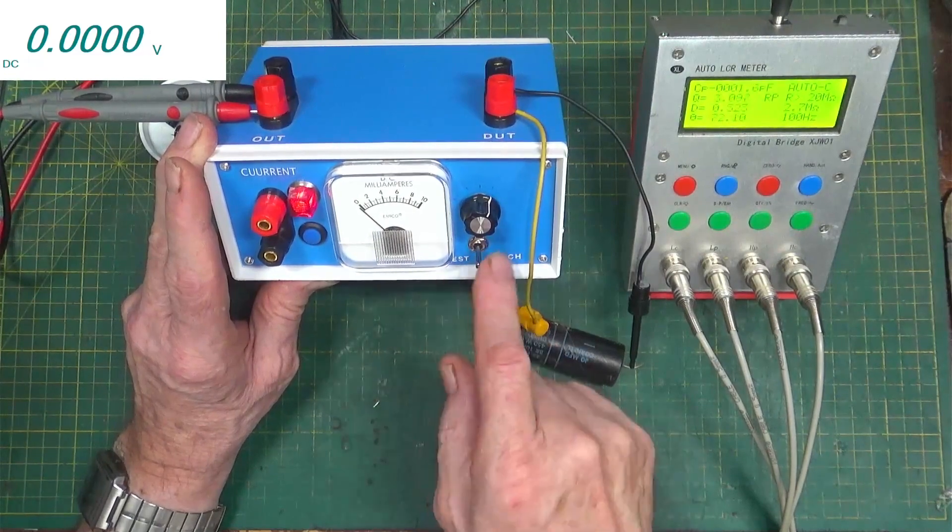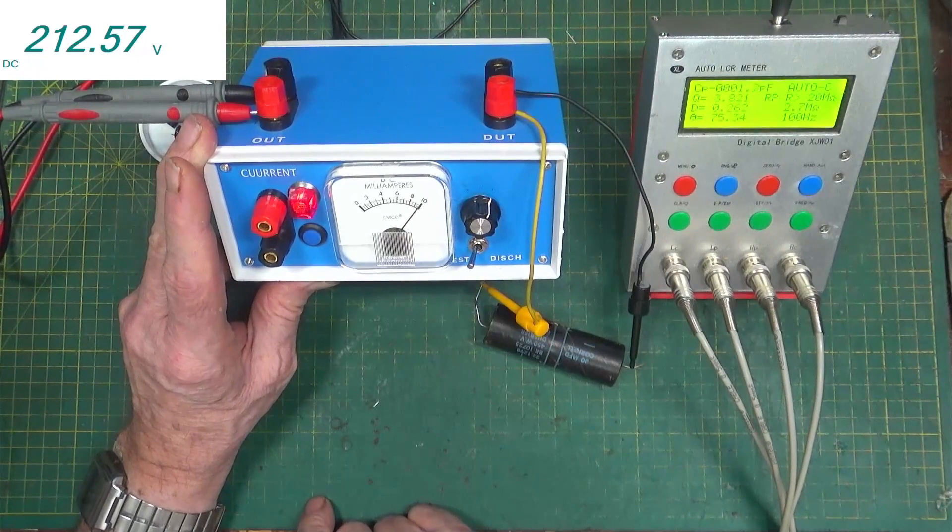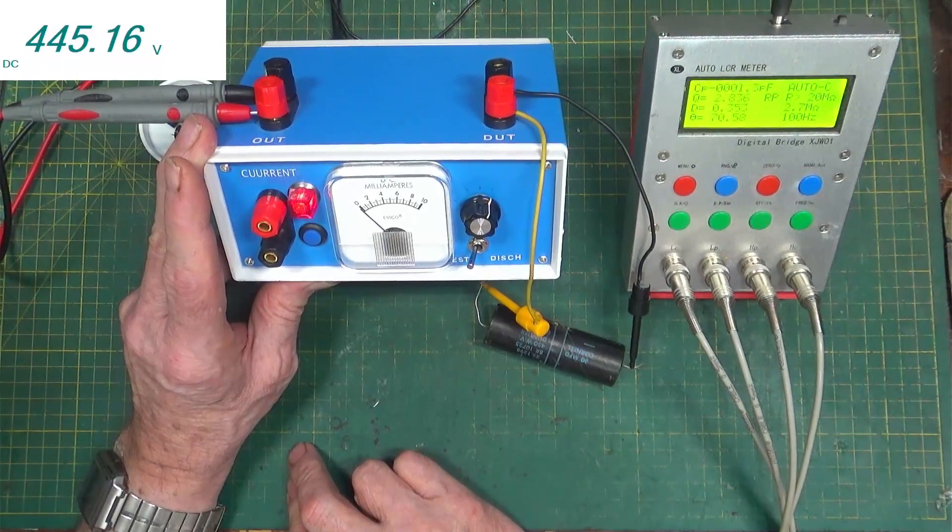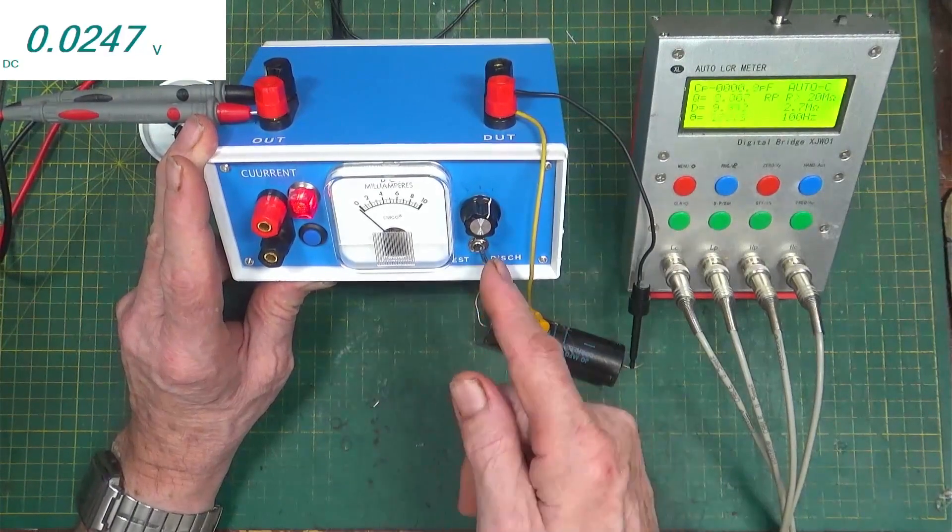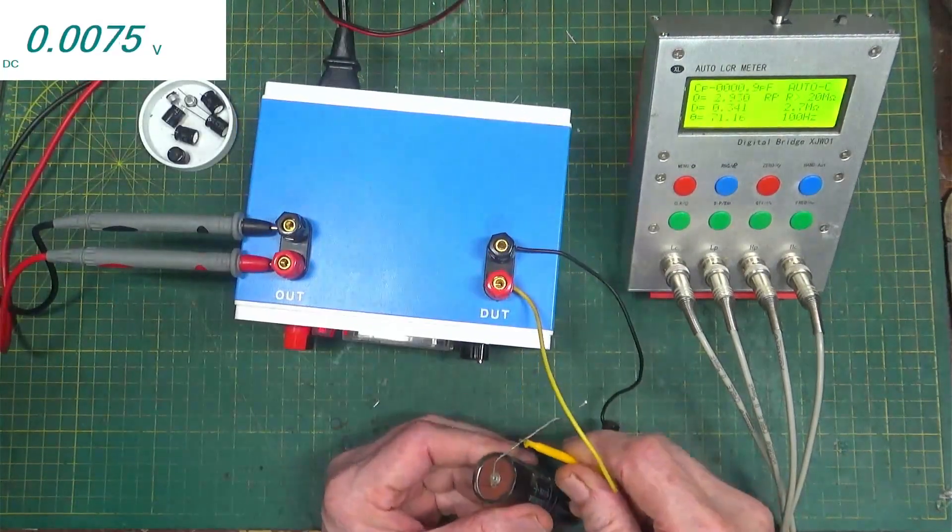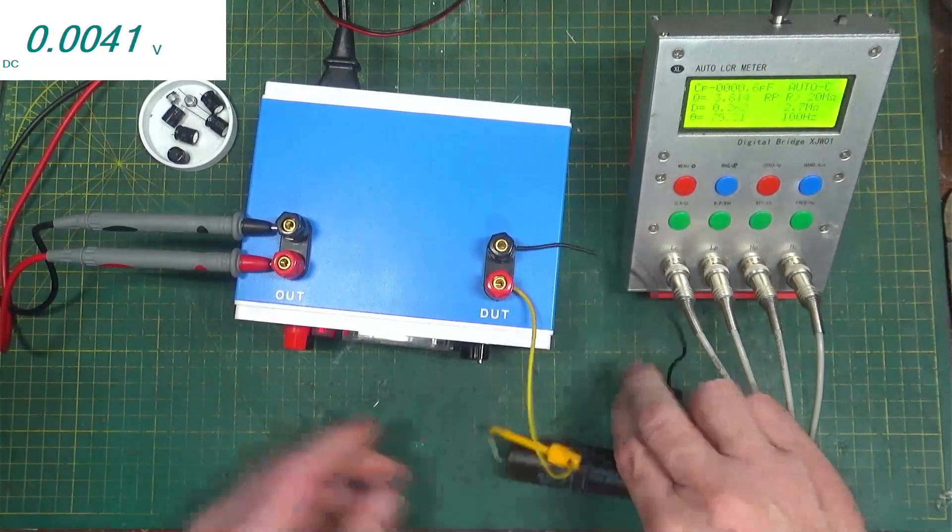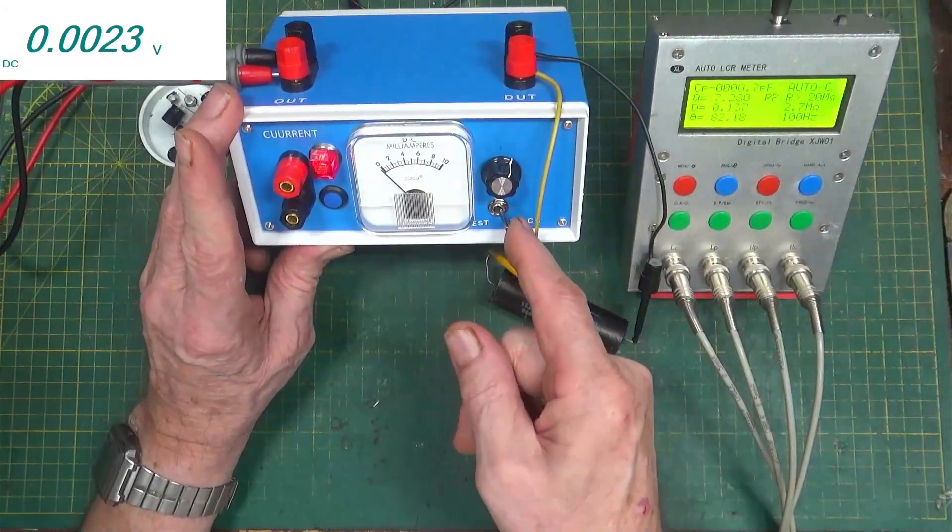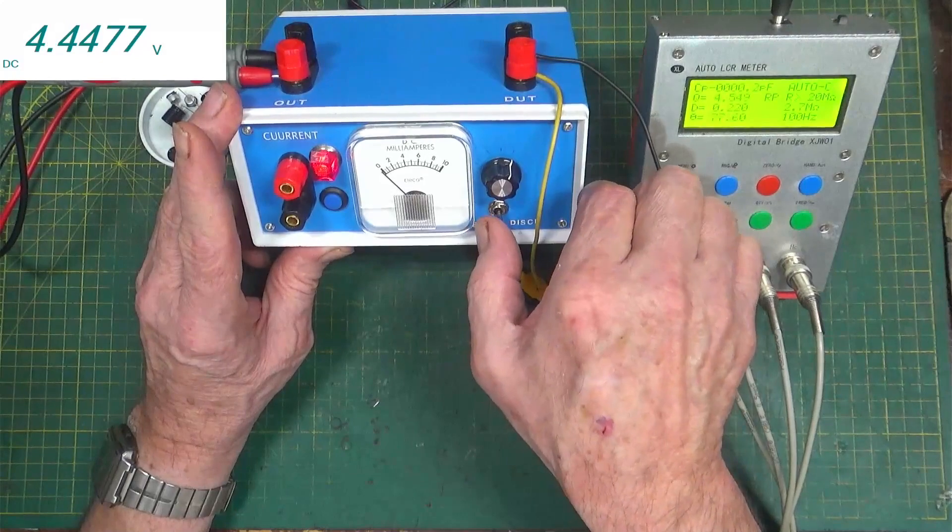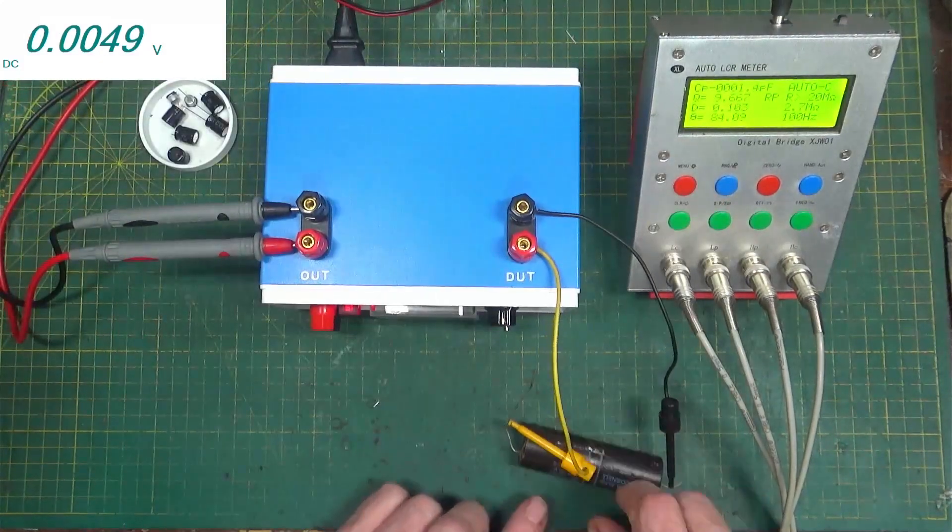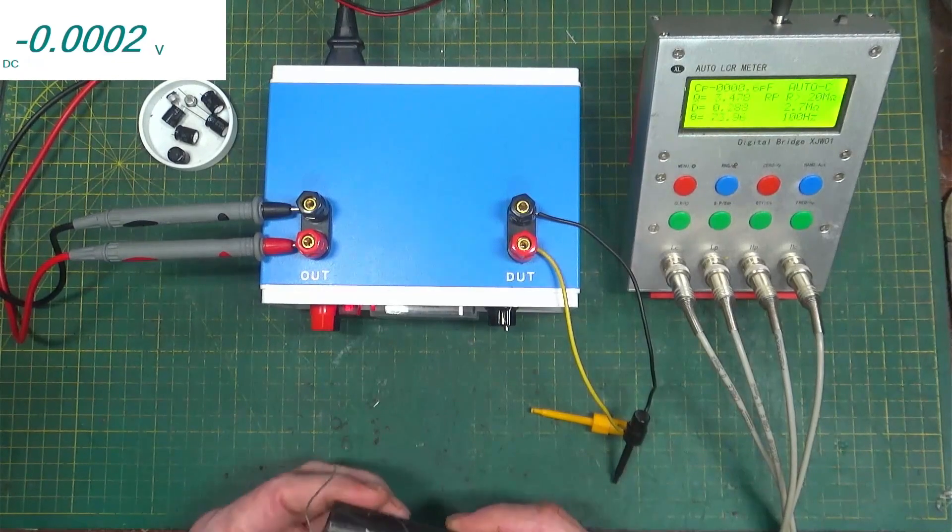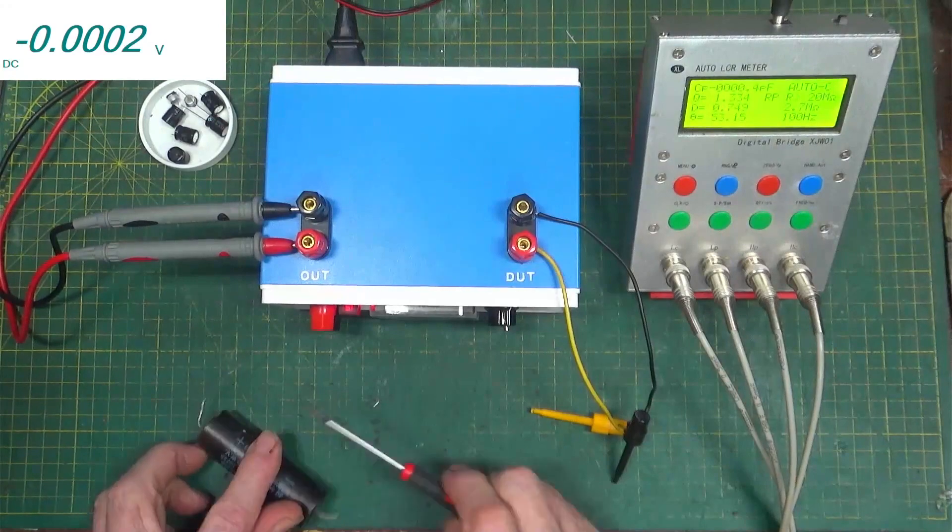Middle is off, right is discharge, then left is test. Yep, slammed all the way over to the top and down it comes. That's a good capacitor, at least it should be. Or I got a bad connection here. I didn't like the way that dropped suddenly. It's going right up to 444 volts. That's what you'll see when these things are working. I'm not sure I like that. It says there's no voltage on the output, maybe we took this out.